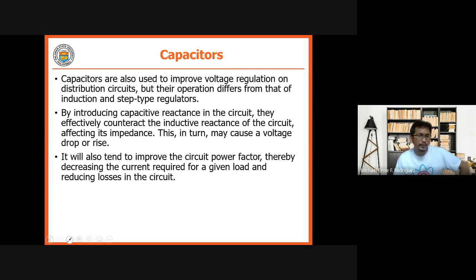Also, what a capacitor does is improve the power factor of the circuit. So when the power factor is improved, the current for a given load is reduced. And when the current is lower, the I-squared-R losses are also lower. So the losses go down—that's what the capacitor does.